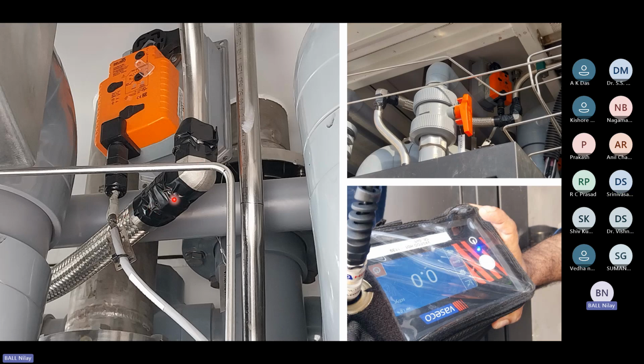At each joint, we use a small sniffer and a pointer, which we push like an injection, inserting the tip of the probe into the joint through this particular black tape, a very high quality tape, and then we measure the hydrogen leakage inside.